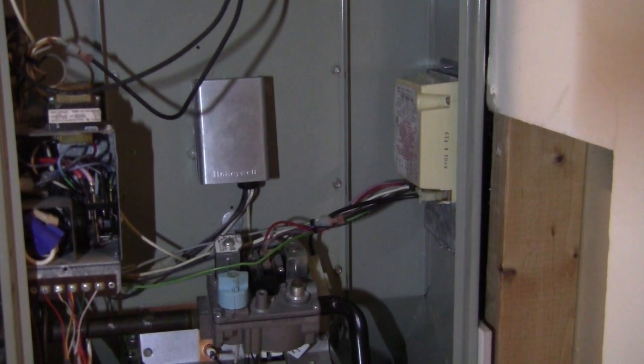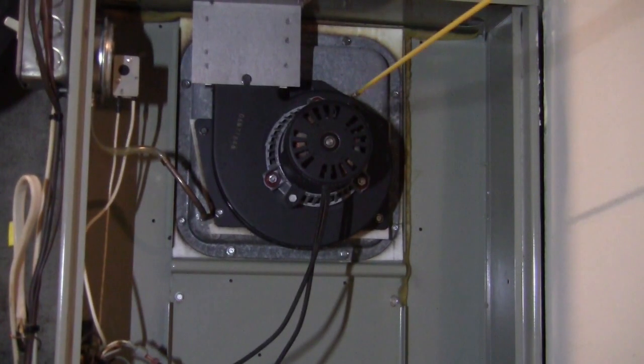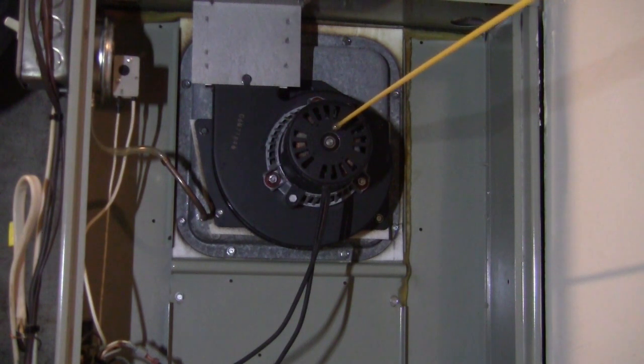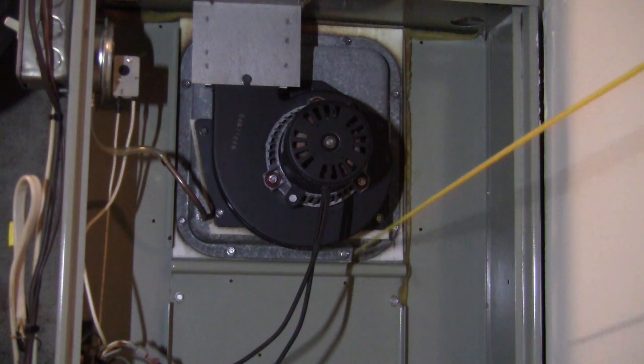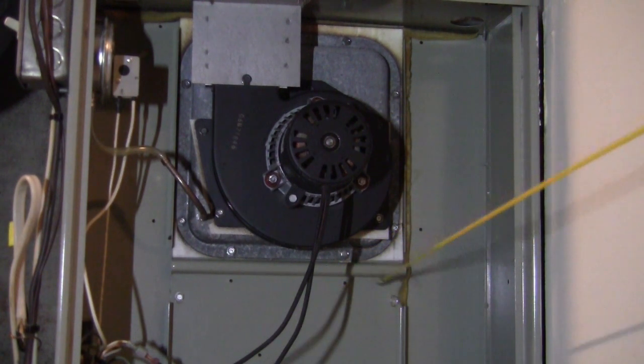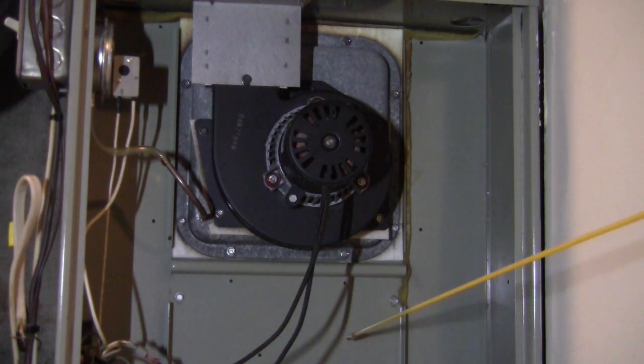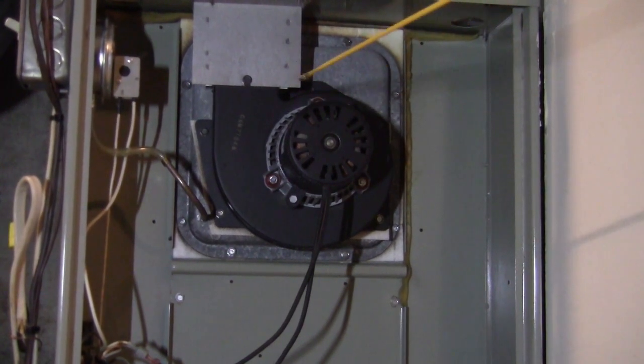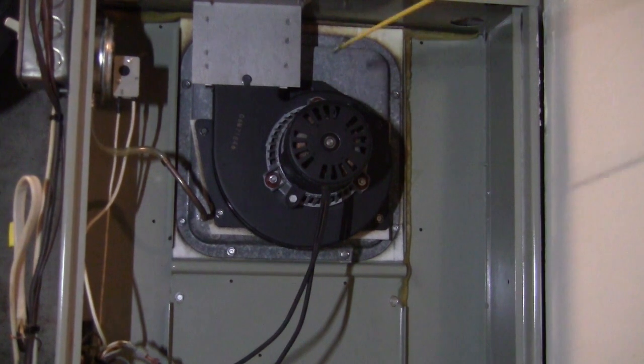So what is the sequence the controller will do for the whole unit? The first thing, it will turn on this fan. This fan is the most important. If this fan is not on, then if you have anything in this chamber, it doesn't matter, gas or fumes or anything inside, it can leak to the outside. And if it leaks to the outside, you're going to get it into your living area. Sometimes it's very poisonous, like carbon monoxide. Sometimes it's very dangerous, like if you have gas leaking. So this fan is the most important part. It has to be turned on before everything else works.